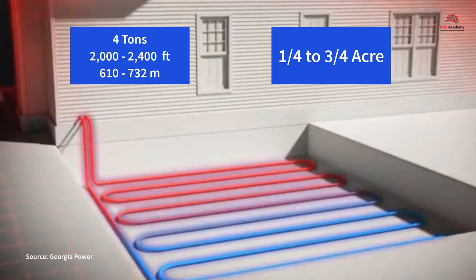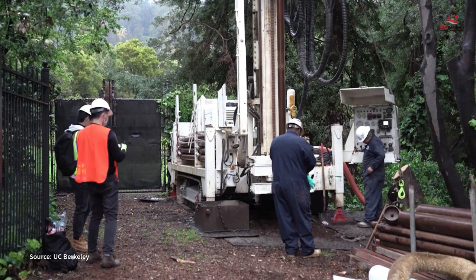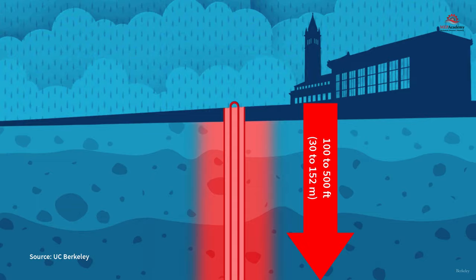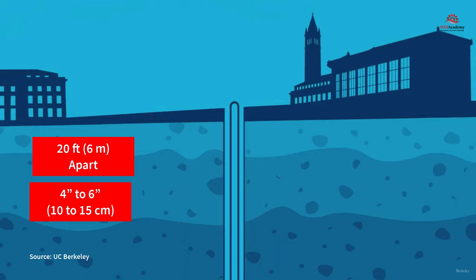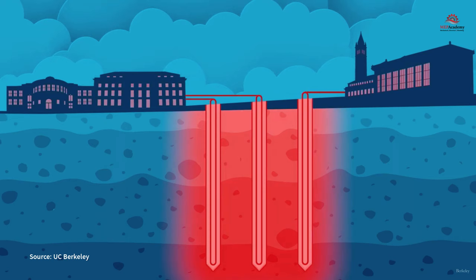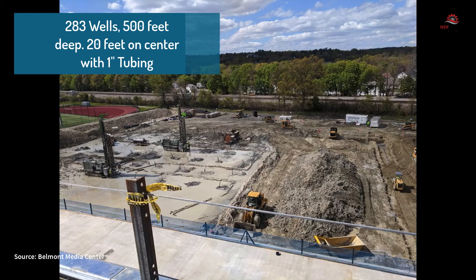Vertical Loop Ground Source Heat Pumps: Using vertical loops requires less land area as the tubing is sent hundreds of feet below the surface. For commercial buildings, this could include boreholes 100 to 500 feet (30 to 152 meters) deep, spaced 20 feet (6 meters) apart to allow for proper heat transfer. These holes can be up to 4 to 6 inches (10 to 15 cm) in diameter and contain plastic tubing that traverses to the bottom where it makes a U-turn and comes back out, connecting to a horizontal manifold. Residential systems would require fewer bores and would most likely be 300 feet (91 meters) deep or less. Vertical loops can be used when there isn't enough land area and when greater efficiencies may be required.